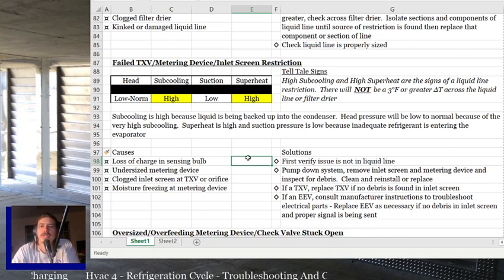It could be a clogged inlet screen at the TXV or the piston or fixed orifice. Almost all metering devices have a little inlet screen right before it. So if you suspect an issue with the metering device, usually you're going to bring a new metering device with you anyway. Install the new one just to cover yourself by the time you pump it down and get ready to put a vacuum on it. The cost difference of a new metering device versus no new metering device isn't enough to worry about.